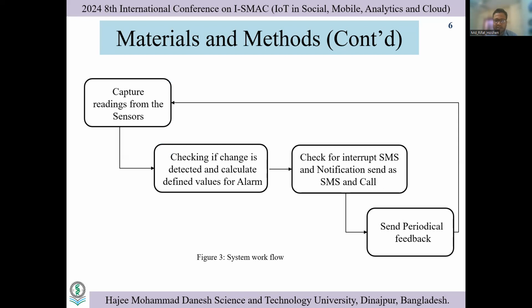The system is designed with a threshold-based approach. It sends a notification once the alarm is triggered. The system sends real-time alerts via SMS and phone calls to predefined contacts. With the periodic feedback, it ensures that the system is always operational. It also sends periodic status updates to the authorities, letting them know the system is functioning properly. This comprehensive workflow ensures both real-time responsiveness and system reliability in preventing transformer theft.